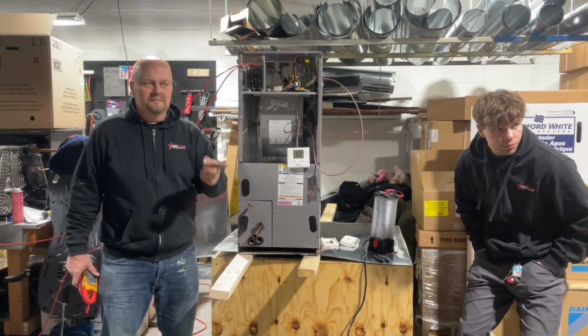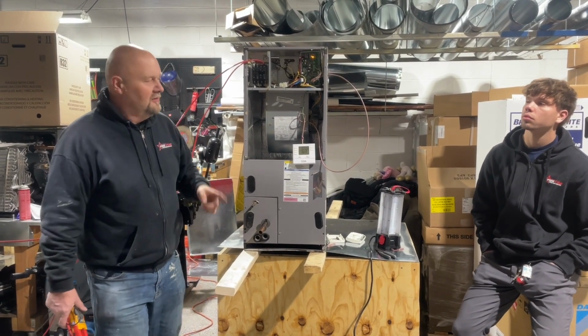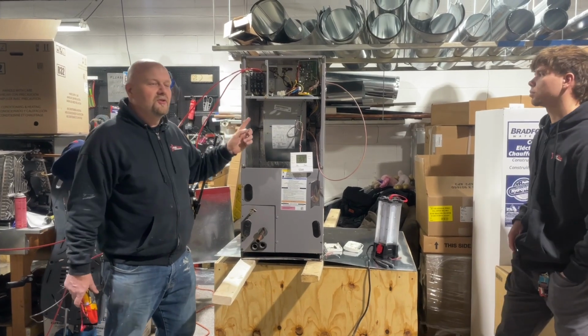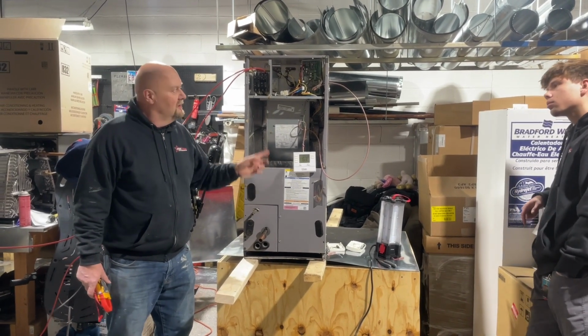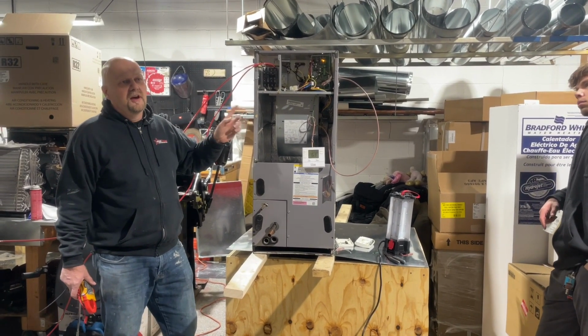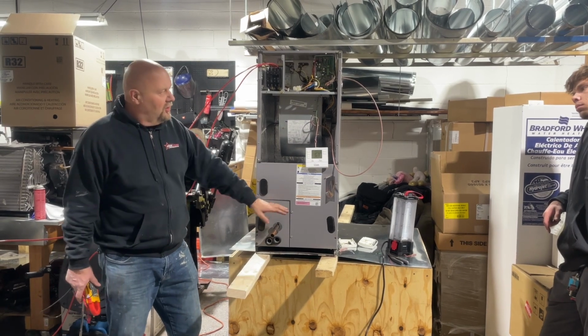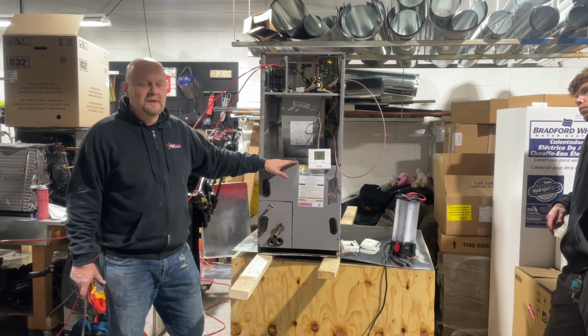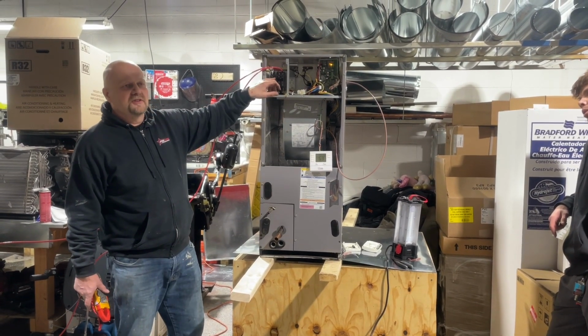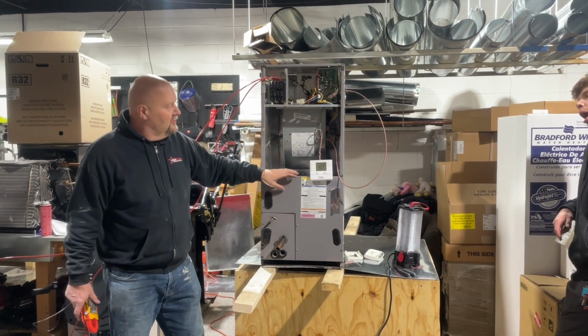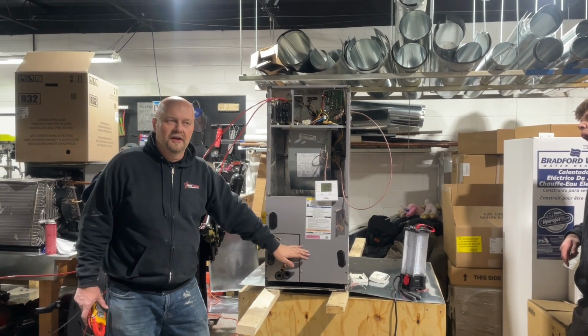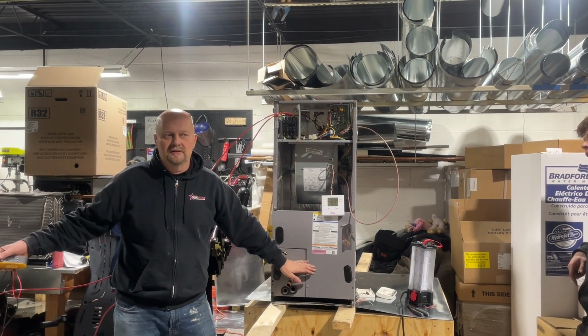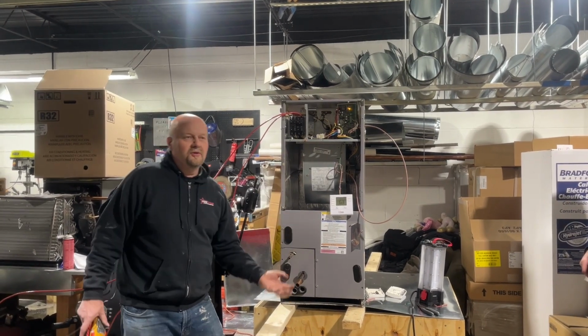Could they both run at the same time? Yes, great question. In this case, you can use both the heat pump and electric heat at the same time. And the reason for that is the coil is below the blower and the electric heat section is above the blower. Meaning you're not going to overheat the coil and cause a problem for the outdoor unit because you're not throwing heat up to it.